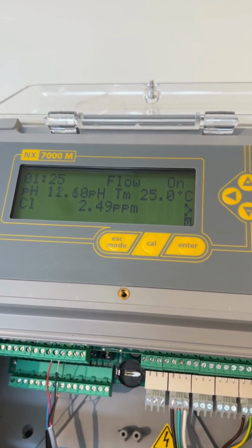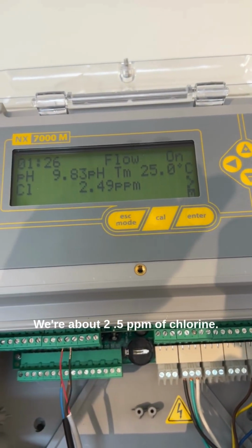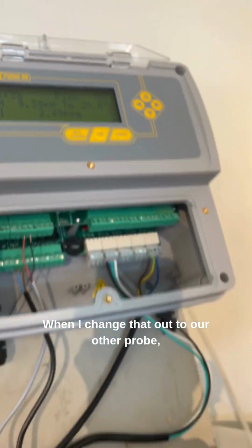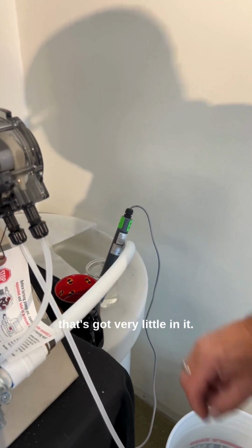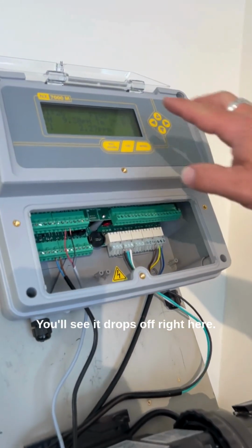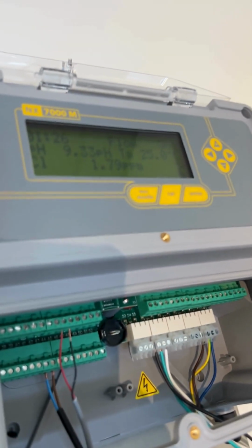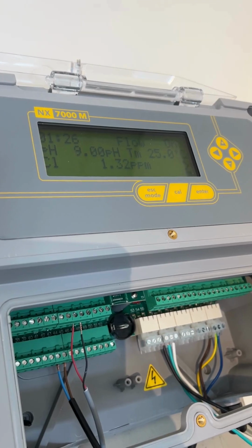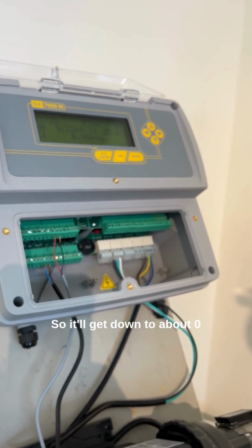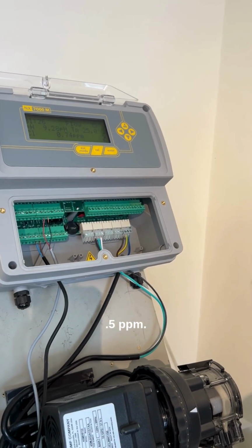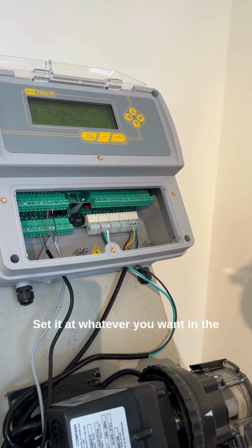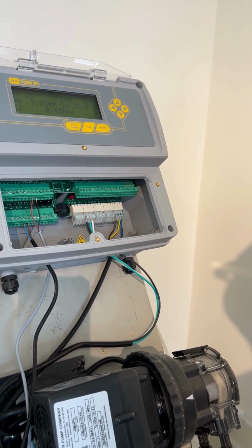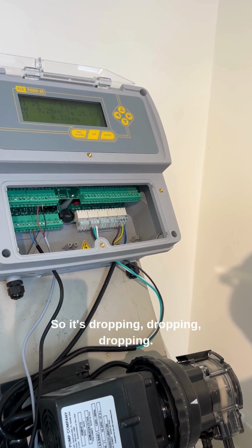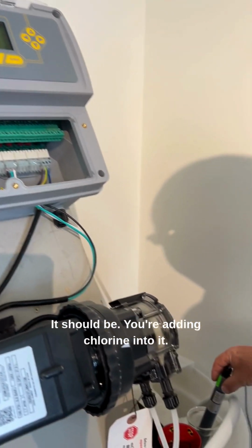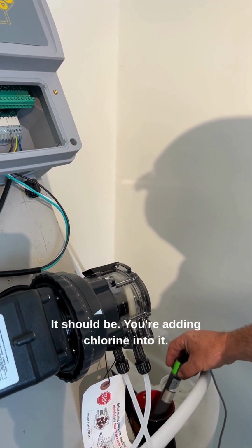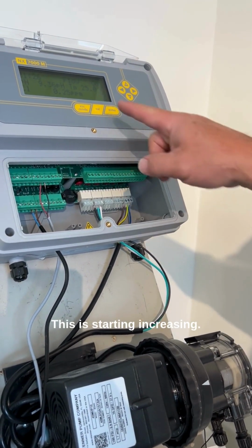Yeah. There you go. So there's where we're at right now. We're about 2.5 ppm of chlorine. When I change that out to our other probe, that's got very little in it, you'll see it drops off right here. So it'll get down to about, we say, 0.5. You can set it at whatever you want in the settings. There she goes. So it's dropping, as it should be. We're adding chlorine into it. I changed it to the other one. This will start increasing.